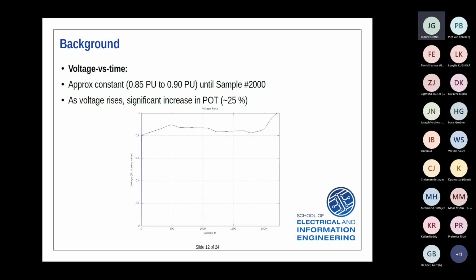So just to give you an idea how sensitive it is, in this case, if we take a straight line across there, which is about 0.85, maybe 0.9, and we then square that to work out the torque, that results in a 25% increase. So just going from 0.9 per unit to 1 per unit changes the torque value by 25%. Okay, so it's extremely sensitive to that voltage. So it's critical that A, the voltage remains constant, or B, that you at least measure it so that you can correct it at a later stage.